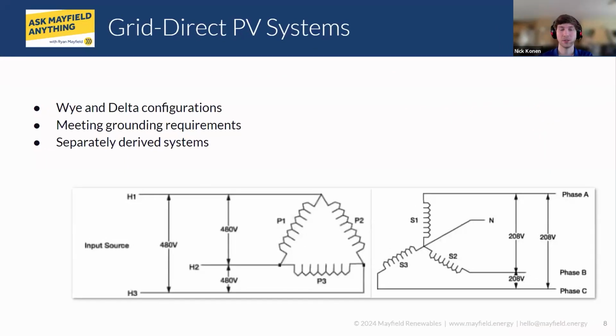And the most common setup we'll see is the delta facing the utility side with the Y side on the inverter side. In battery storage, it just flip-flops around a little bit, where often the BESS wants to be an ungrounded system. So typically it's a delta facing the BESS side. And then with an absence of the grid only being powered by the BESS, it's good then to have that Y neutral there on that grid facing side to provide those single phase loads.